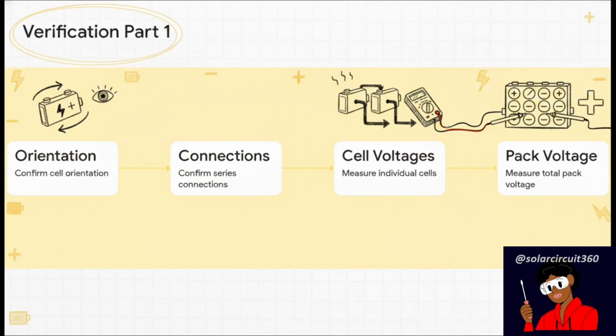Step 1: visually confirm the orientation of every single cell so you absolutely do not have reverse polarity. Step 2: physically confirm your solid series connections. Step 3: take your multimeter and measure every individual cell to make sure their voltages are consistent. Step 4: measure the total pack voltage — it should perfectly equal the sum of those 8 cells we talked about earlier.